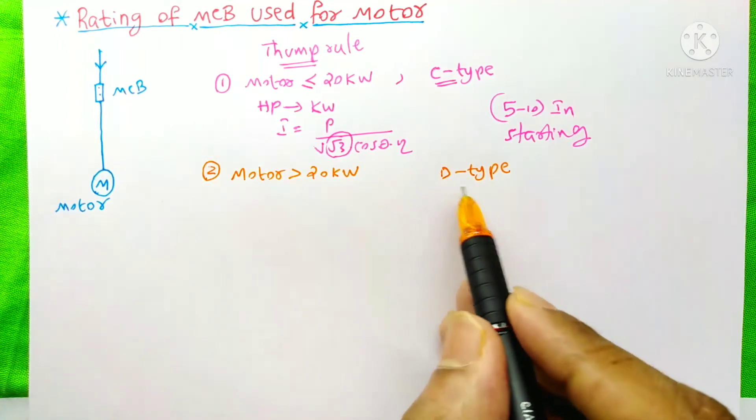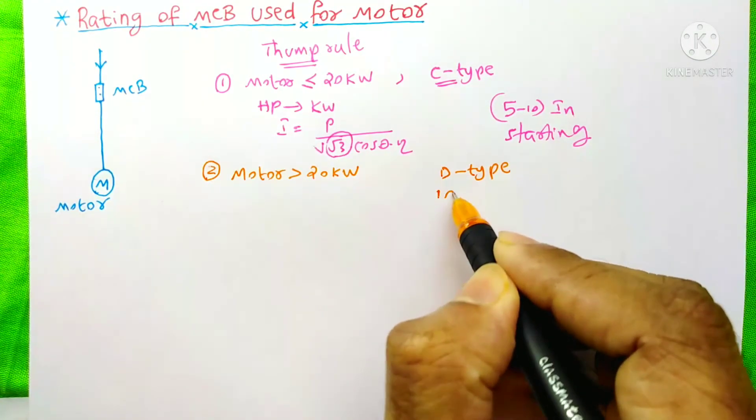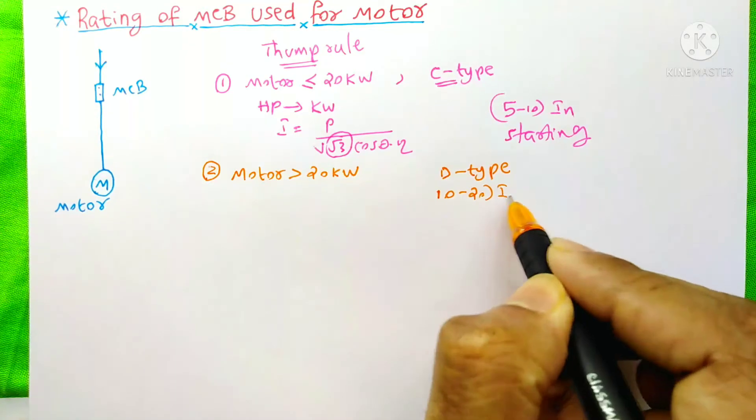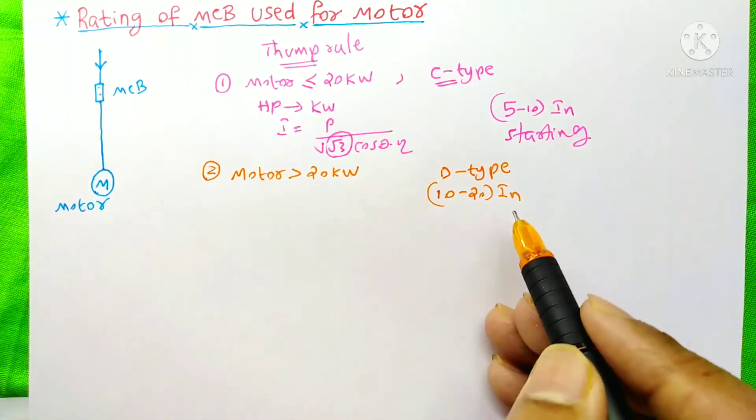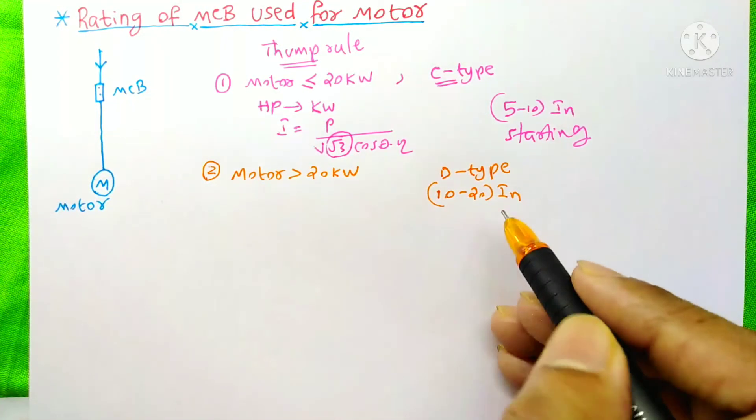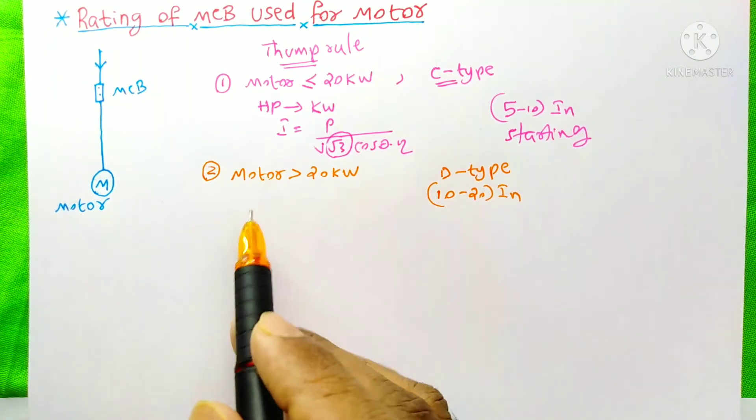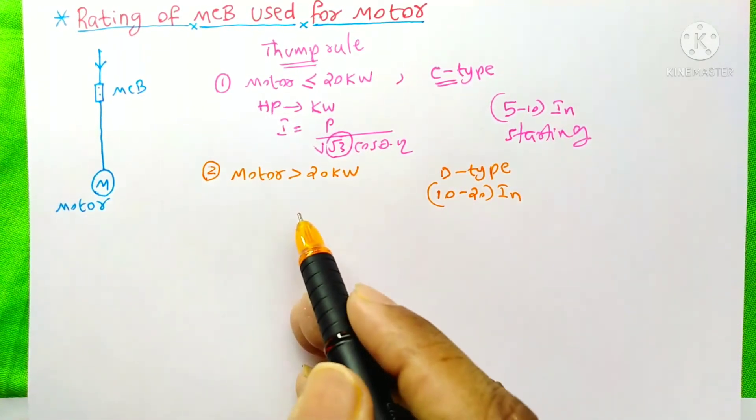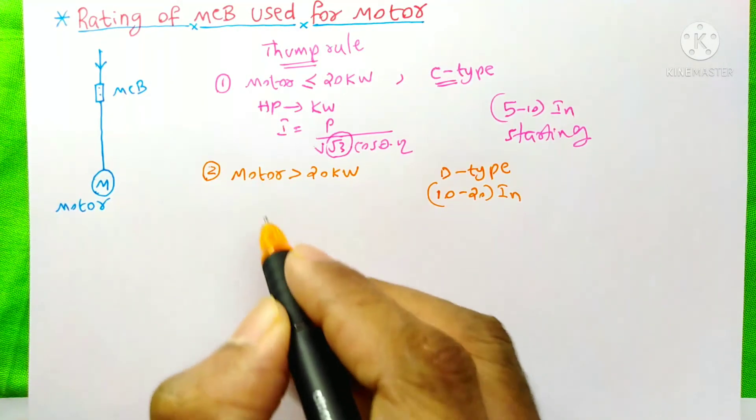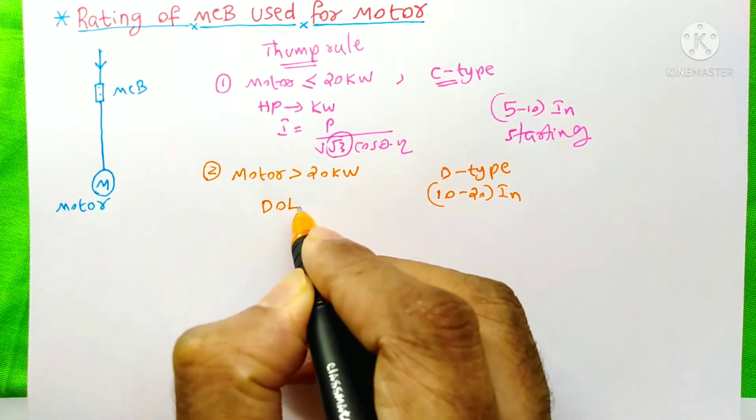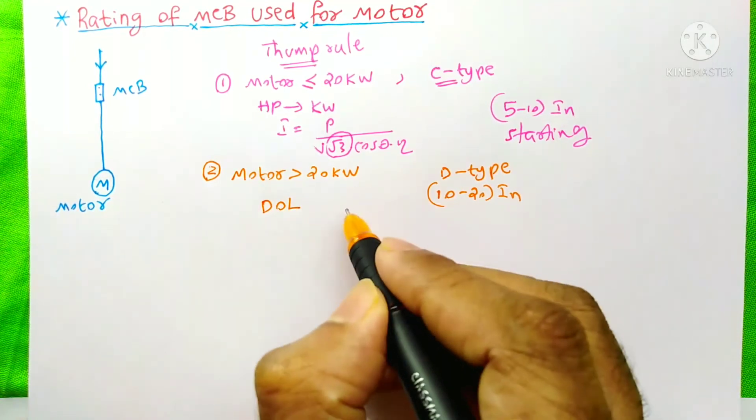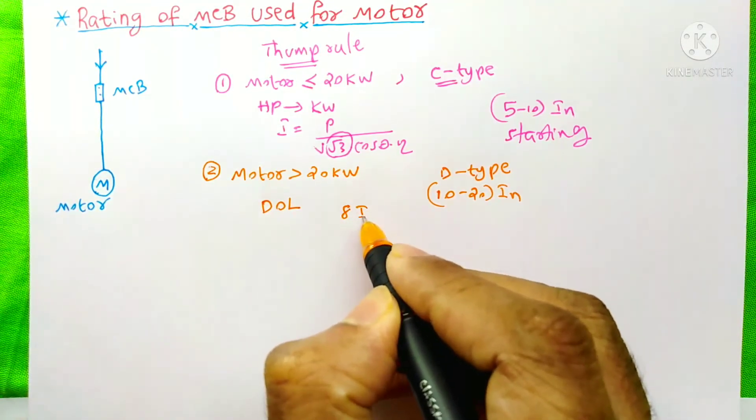We know that D-type MCB will allow 10 to 20 times of the rated current for a short duration of time during the starting of the motor. Generally we know that during the starting of motor, even if the motor is charging with the help of a DOL starter, it would take 8 times of the rated current.